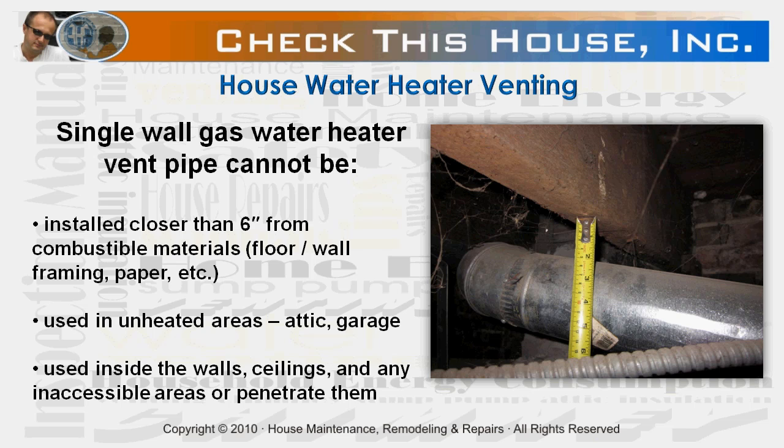Number two: single wall gas water heater vent pipes cannot be used in unheated, unconditioned areas like attic, garage, or crawl space, even if only partially penetrating that space. Such installation will cause excessive condensation on vent pipe walls and compromise proper drafting. Double wall B vent pipe is required for those applications. And number three: single wall gas water heater vent pipe cannot be used inside walls, ceilings, or any inaccessible areas. Again, double wall type vent pipe — B vent — must be installed in those cases.